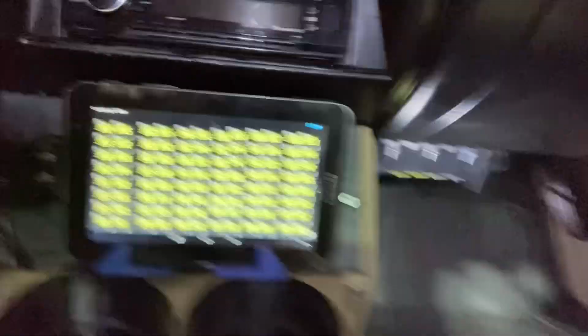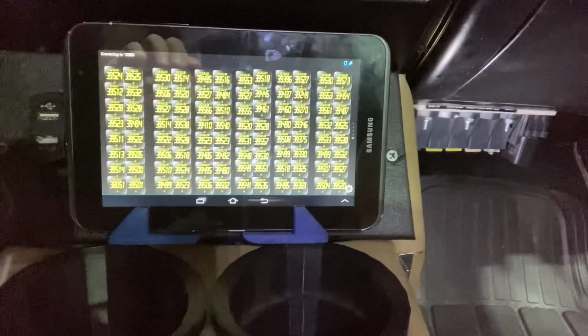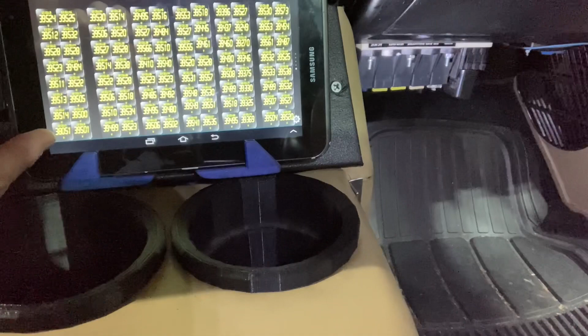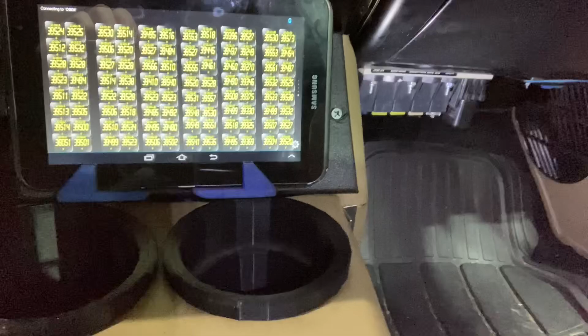That's basically what it was before I turned it off a second ago, but that's what it's reading right now. The problem is this cell down here is 3.8051, about 150 millivolts off from what's actually read at the cell. Because I checked the module in a previous video, and it was reading 3.9. So I'm going to check the BMS wires and see if it's reading 3.9 or 3.8, then go from there.